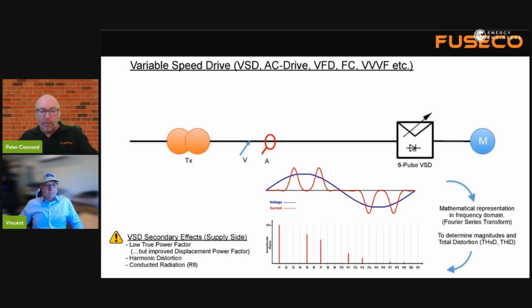So with harmonics, I think it's important to understand that it's purely in electrical engineering for supply side analysis like this. It's purely a mathematical representation. And it's limited. According to IEC standards, Australian standards, we're looking at a restricted frequency range. We're not talking about high frequency EMC or RFI or other aspects of power quality that can also be analysed in a similar way. We're just talking about how to understand these lumps and bumps. These lumps and bumps are impacting power quality, and as a result, kVA hour as well. Next slide, please.